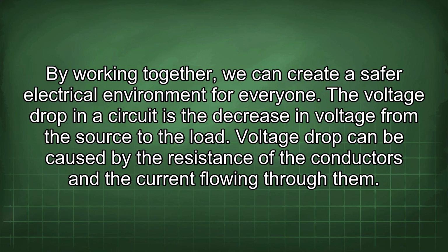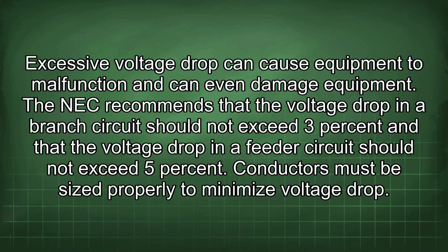Voltage drop can be caused by the resistance of the conductors and the current flowing through them. Excessive voltage drop can cause equipment to malfunction and can even damage equipment. The NEC recommends that the voltage drop in a branch circuit should not exceed 3% and that the voltage drop in a feeder circuit should not exceed 5%. Conductors must be sized properly to minimize voltage drop.